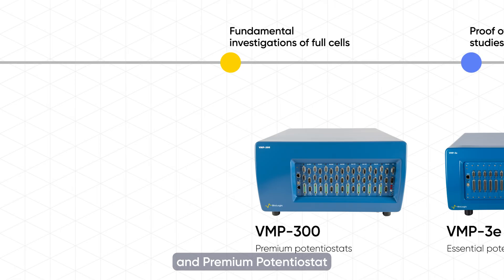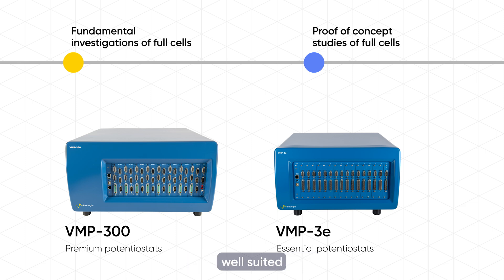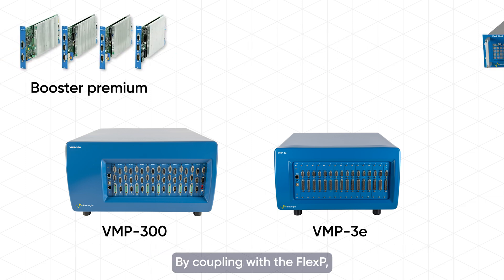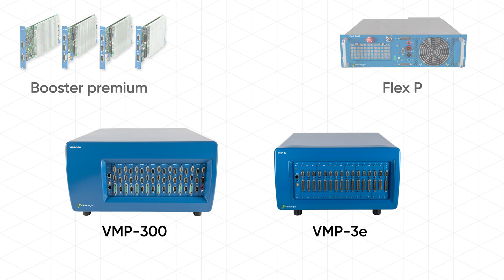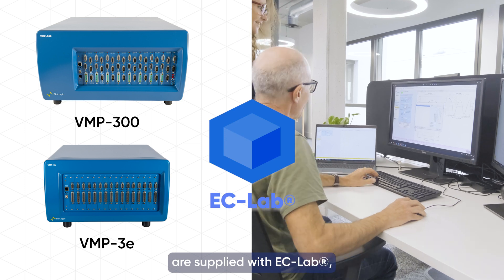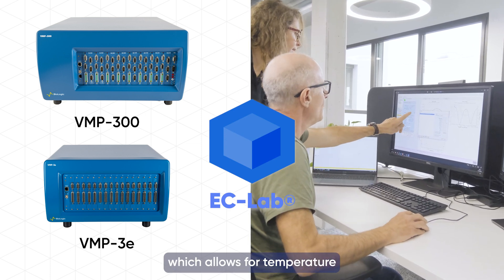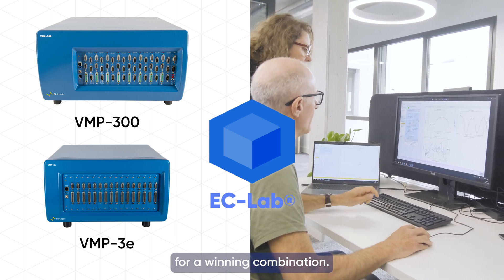Biologic's essential and premium potentiostat ranges complement each other, and although both are well-suited for fundamental and full cell studies of ASSBs, the essential range, including the VMP-3e, is perfect for high-voltage studies. By coupling with the FlexP, users can achieve up to 60 volts. All Biologic potentiostats are supplied with EC-Lab, our benchmark control and analysis software, which allows for temperature control and climate chamber management.